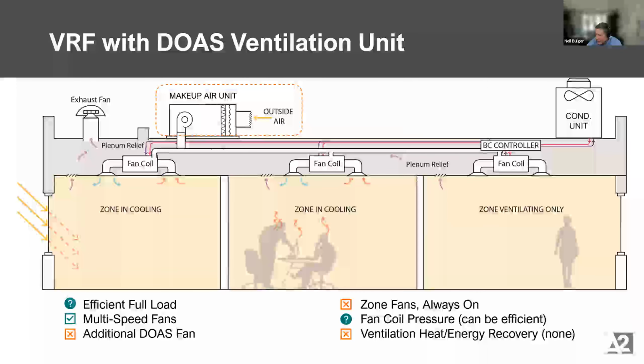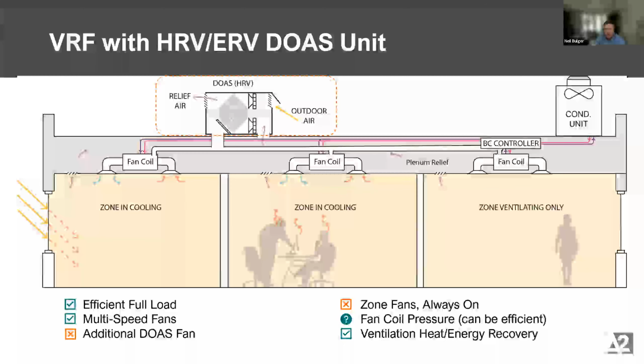I don't know if I would change the performance curves of the products. I think the curves that were used were built off reviewing engineering data from several different VRF manufacturers to try and figure out how these units perform at different wet bulb temperatures and outdoor temperatures. When you do have a dedicated outside air system that serves your building, it certainly can impact the size of the coils. And I think in the software, you can even say, should my unit account for that and downsize the fan coil? It's always good to check though. A lot of designers won't, they'll assume they'll size it anyway.